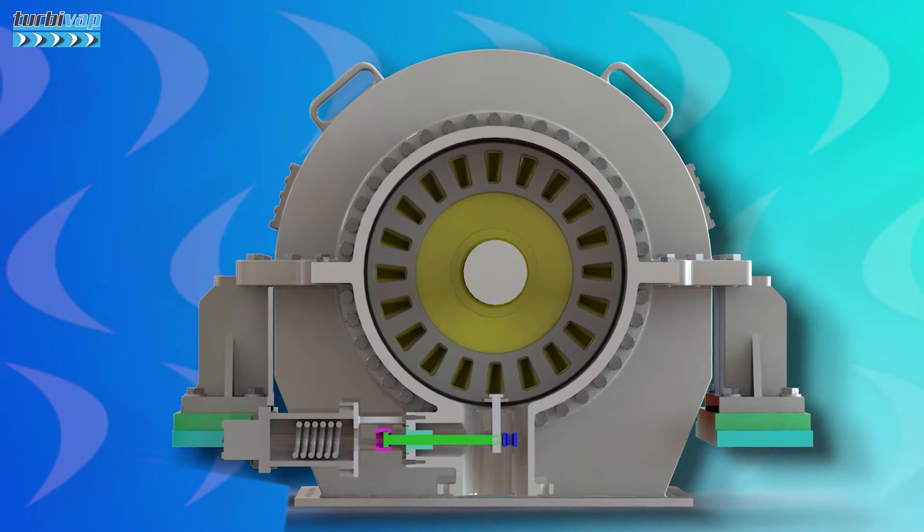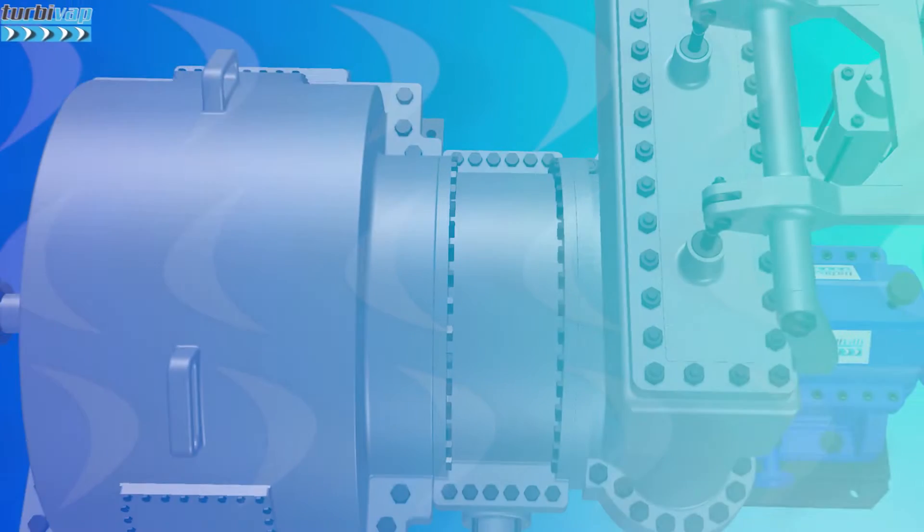Regenerative cycle extractions use steam from inside the turbine for heating boiler feed water, and are almost always of the uncontrolled type. They have the advantage of being low cost and easy to operate. They are normally used to power cycle equipment such as deaerators and preheaters, and for industrial processes that do not require constant pressure.